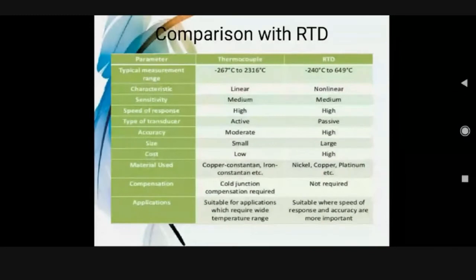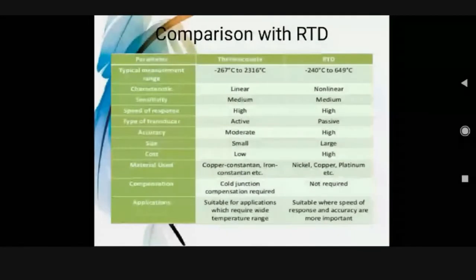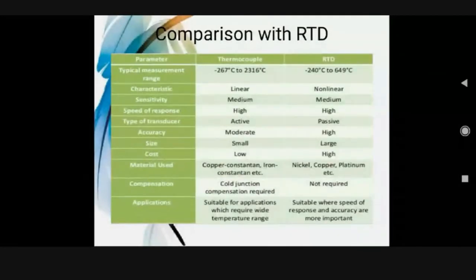Okay, now we will see a comparison of RTD and thermocouple based on some points. Typical measurement range: thermocouple is minus 267 degrees Celsius to 2316 degrees Celsius, and RTD is minus 240 degrees Celsius to 649 degrees Celsius. Characteristic of thermocouple is linear and characteristic of RTD is non-linear.